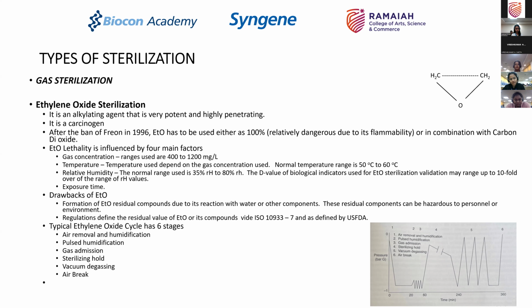And there is a guideline which talks about the quantum of residual ethylene oxide or its compound which should be present after the sterilization process is over. This is defined as per ISO 10993-7 and also by the US FDA.